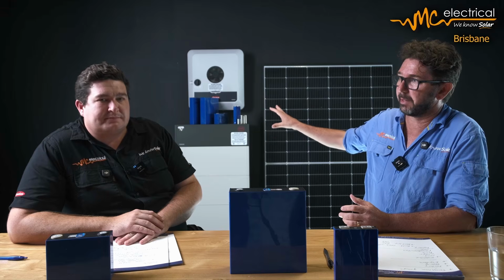Okay, so to quickly explain it, just to give you round figures, let's say you put 10 kilowatt hours of power into your battery. You would expect to draw maybe 9 out of it because you're going to lose a little bit on the efficiency, right - maybe less if you're pulling it out slower. So when we test these high voltage batteries, and this is the same with all the high voltage batteries we've done - Fronius, BYD, Fox.